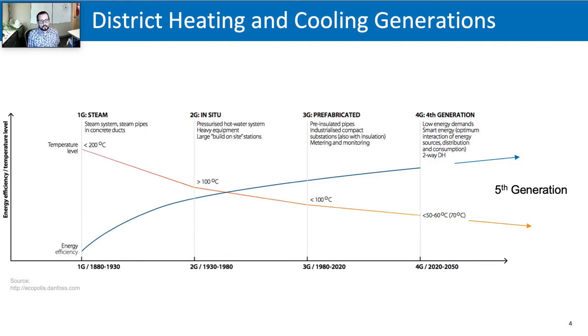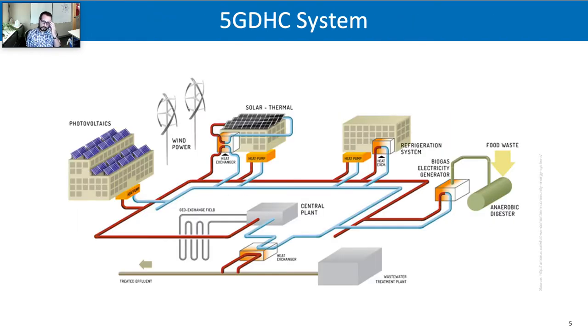Efficiency was way up though, because now you're not heating water as hot as before, so your losses are less. What we're really interested in is modeling fifth generation systems, sometimes called ambient loop systems. This is where you get water at near outdoor ambient temperature, between say 15 and 25, maybe 20 to 25 degrees Celsius. What's nice about those systems is that buildings can supplement heating or cooling as needed with a localized heat pump. In this image, you'll see heat pumps attached to each building to either increase or lower the temperature needed for that building.